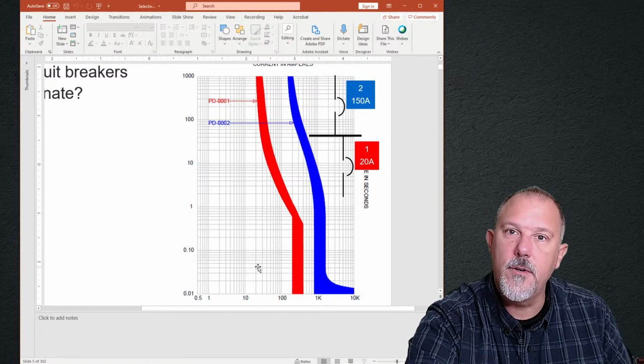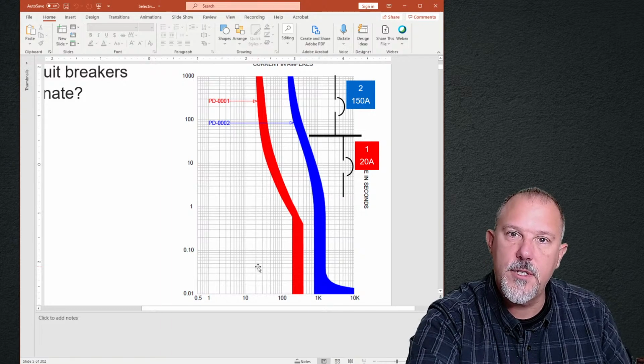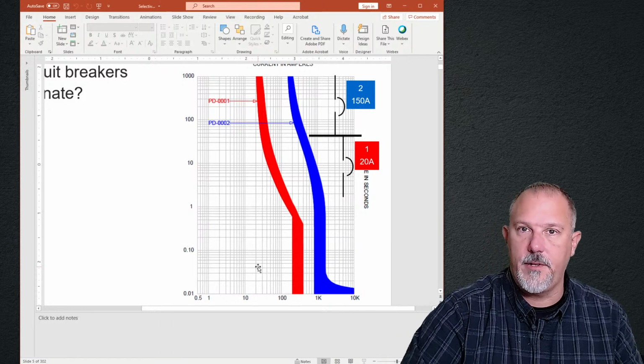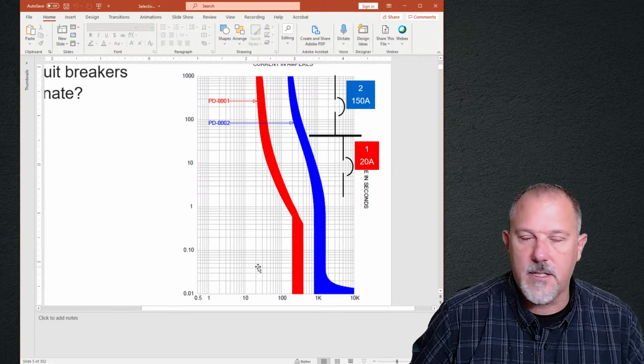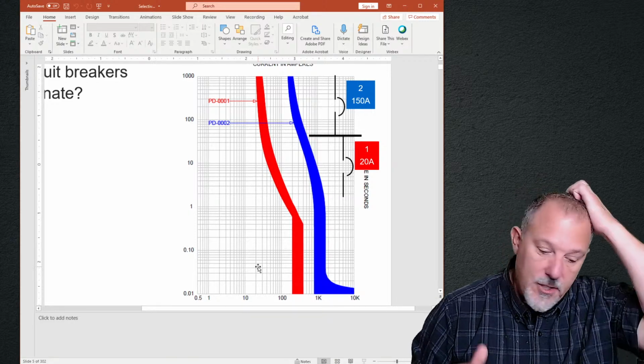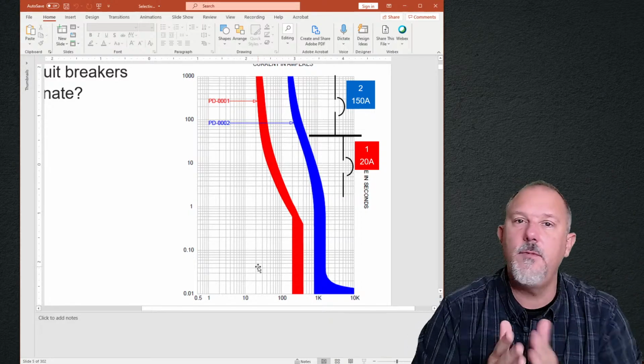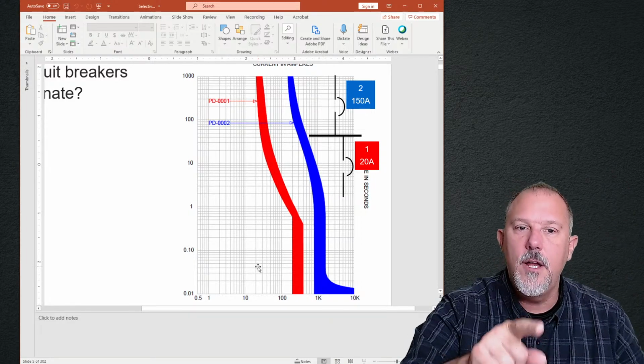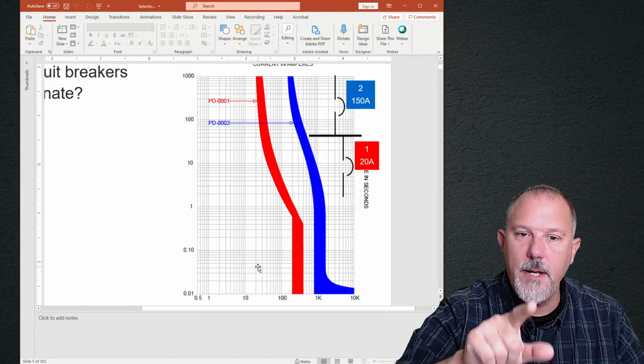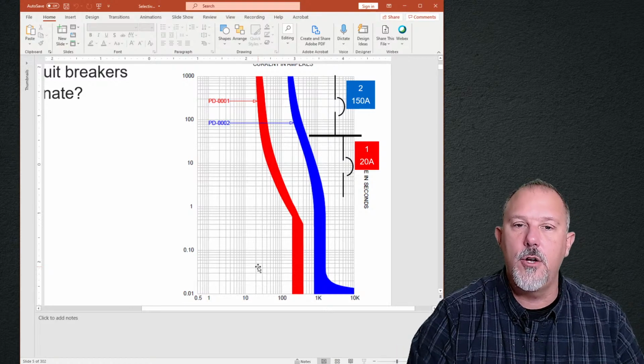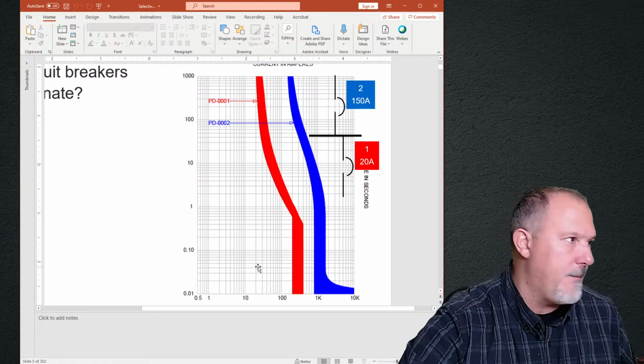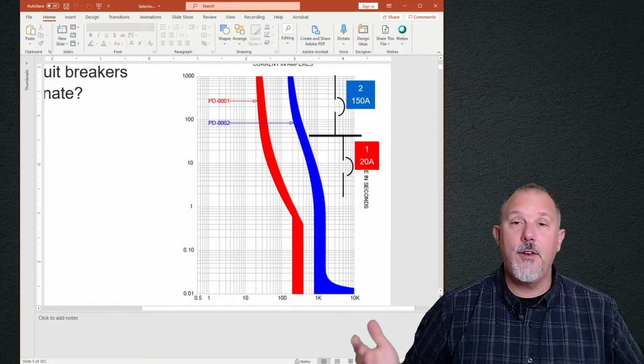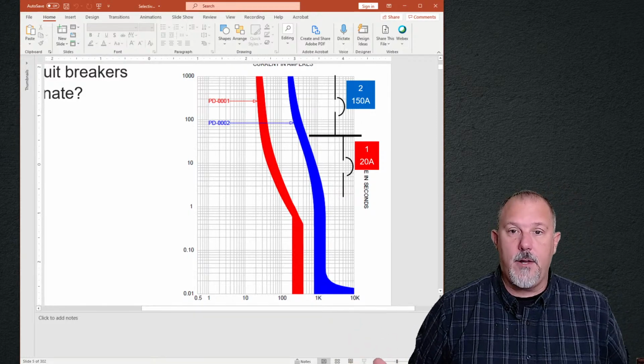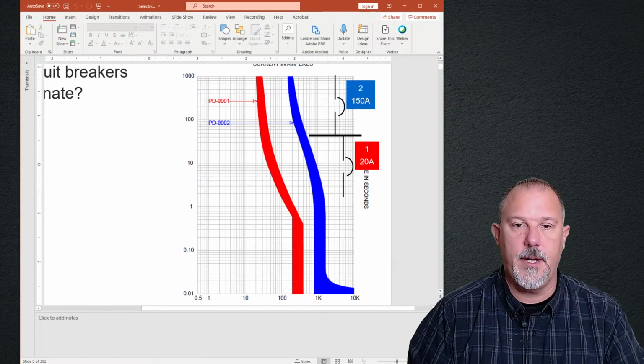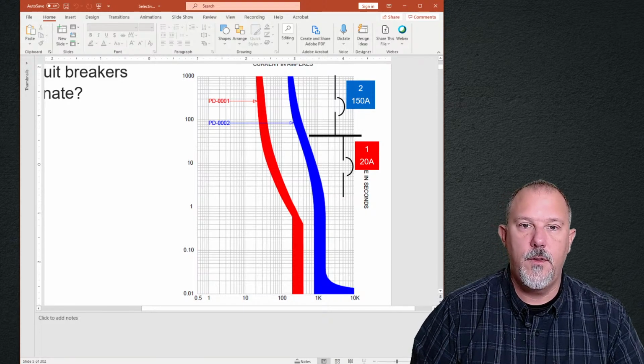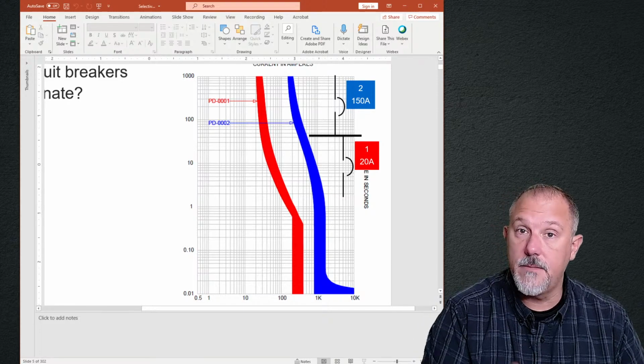What is my fault current? What current are you going to selectively coordinate these two, or coordinate these two, if it's less than the three-phase bolted fault current value? And that individual disagreed with me again, and they said, no, that downstream breaker will open and the upstream breaker will remain closed even for 10,000 amps. And so how do you handle that one? I mean, how do you argue with somebody that is not the case?